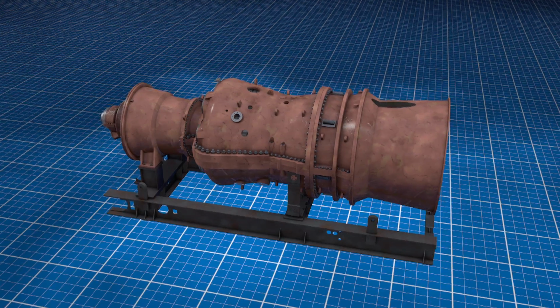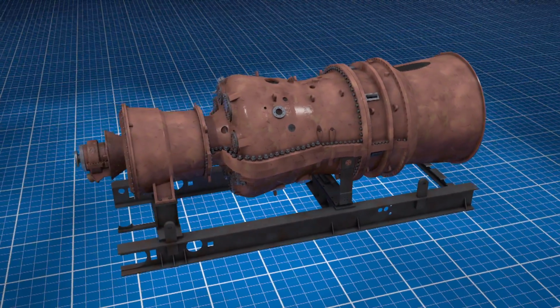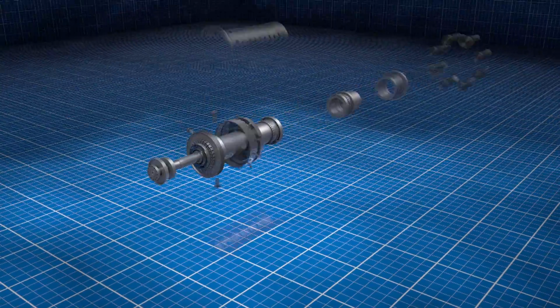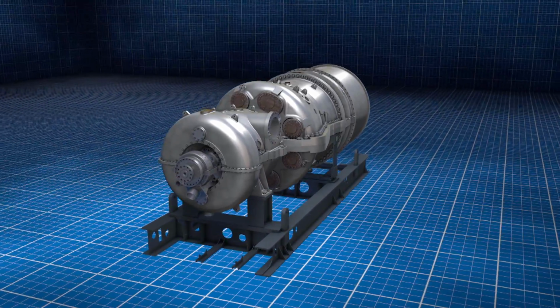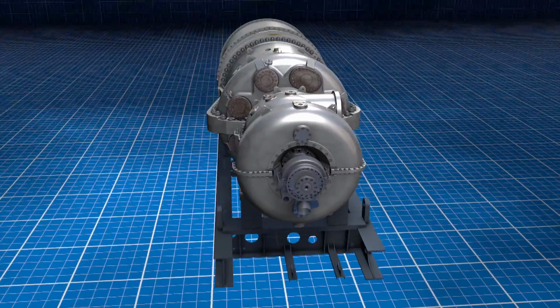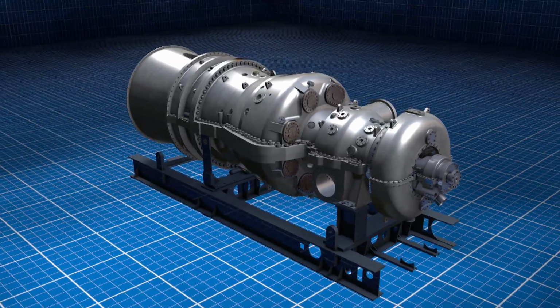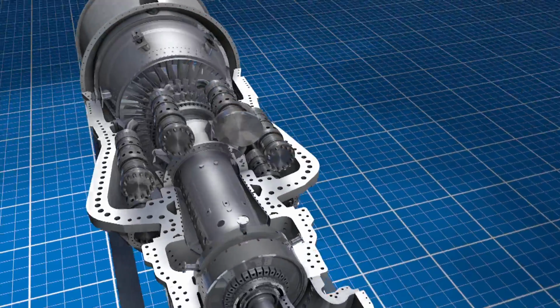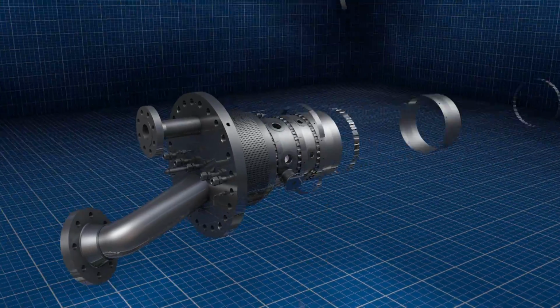To fully exploit the capabilities unlocked by CES technology, CES, in collaboration with Siemens and sponsored by the Department of Energy, redesigned the existing 43-megawatt SGT-900 for oxy-fuel combustion, making it the oxy-fuel turbine, or OFT900. Future units of the OFT900 will be known as Siemens Expander Turbines, or SXT-150. The primary advancement of the OFT900 lies in the replacement of traditional combustor cans with reheater oxycombustors that work based on the same principles as the CES gas generator.